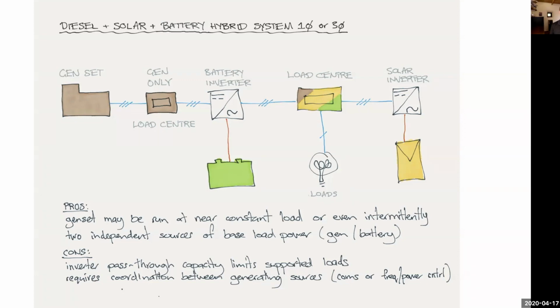It also gives you the possibility where the battery inverter can parallel with another source, like a generator, to sum the two together. You might have a 10 kVA generator set and a 5 kVA inverter, but you can actually supply 15 kVA through to the loads because they can be synchronized together. So, synchronizing sources. I think I've mentioned that one of the cons was that it does require communication. The other one is that you do need to consider the pass-through capabilities of that battery inverter if you're using the internal contactor. Many battery inverters with two ports, a generator port and a load port, have an internal contactor, and they might be rated something like 30 amps, 50 amps, 63 amps, 125 amps even.